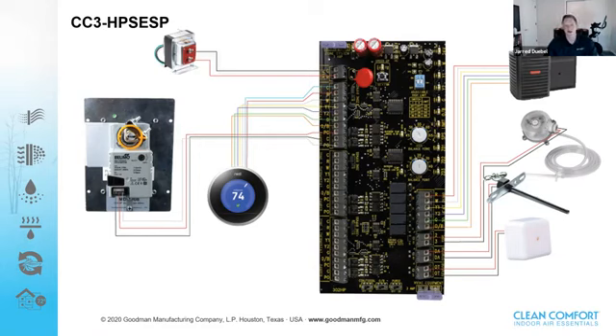On the flip side of that, we can set a high balance point where we say, hey, anytime we're above this temperature, we're only going to use our heat pump because it's most efficient. So let's just say, for sake of an example, I'm going to set that at 35 degrees Fahrenheit. So at that point, anytime we reach or exceed 35 degrees Fahrenheit outside, we're only going to use that heat pump for first or second stage.